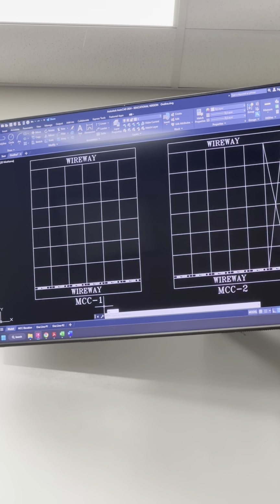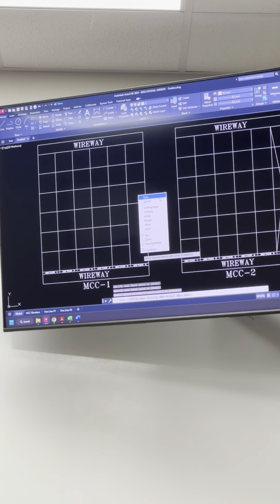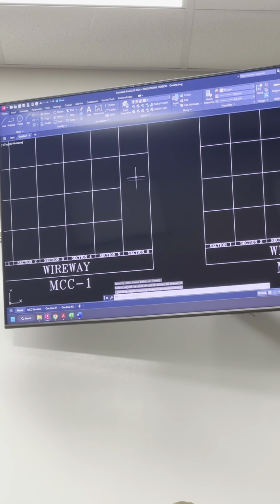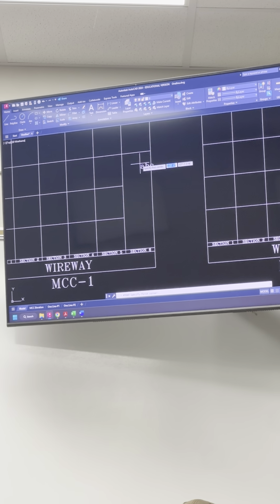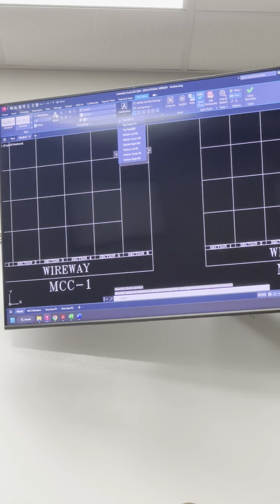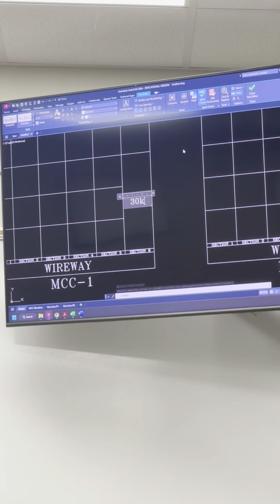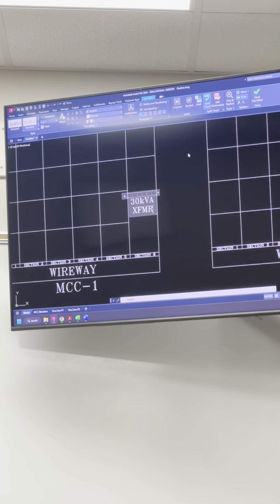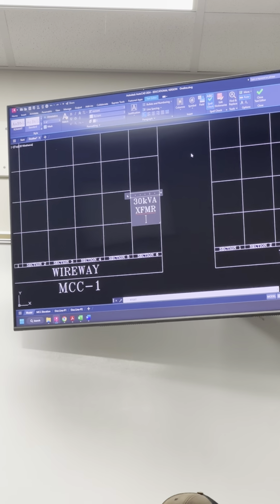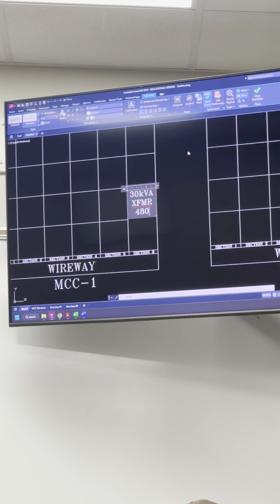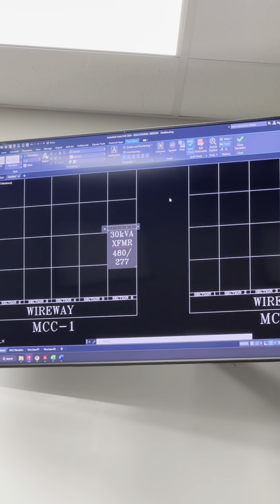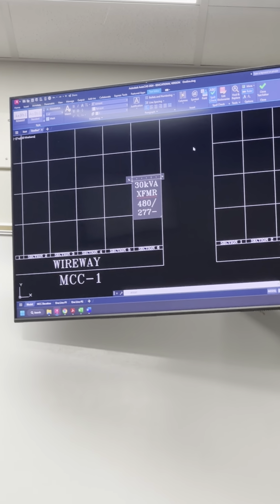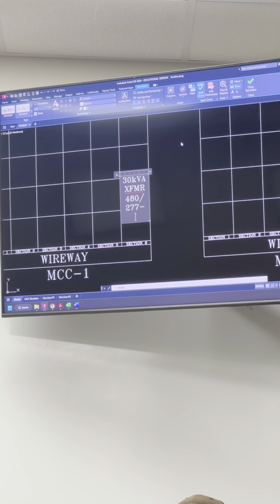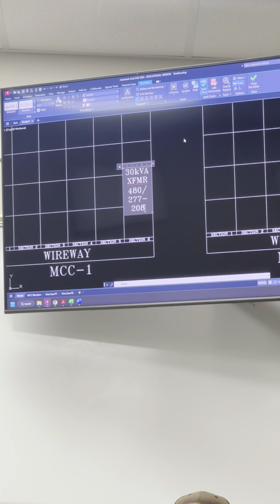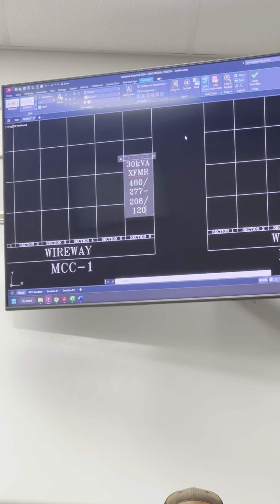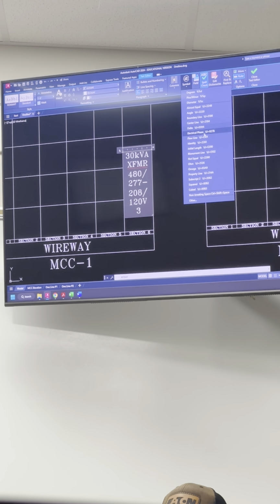Since it's 3 space factor, we're just gonna visually represent that—I'll delete those 3 lines to show the 3.0 space factor, and put some text in there. We'll say 30 kVA, and that it's a transformer, then list out the voltages: primary phase to phase, 480, over primary phase to ground, 277, dash to indicate we're done with primary and switching to secondary. Same thing: secondary phase to phase, 208, over phase to ground, 120 volt. And we'll also list it as a 3-phase transformer.